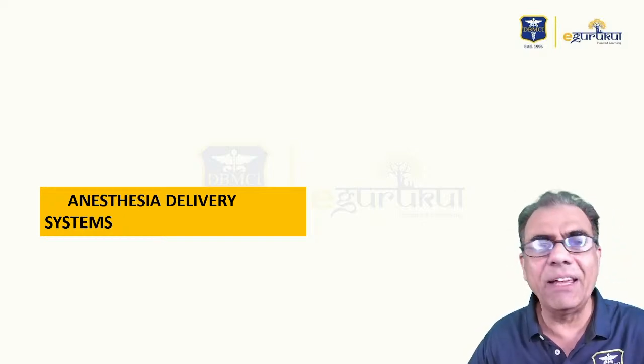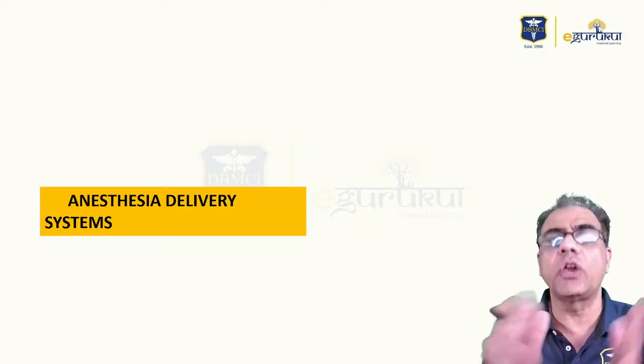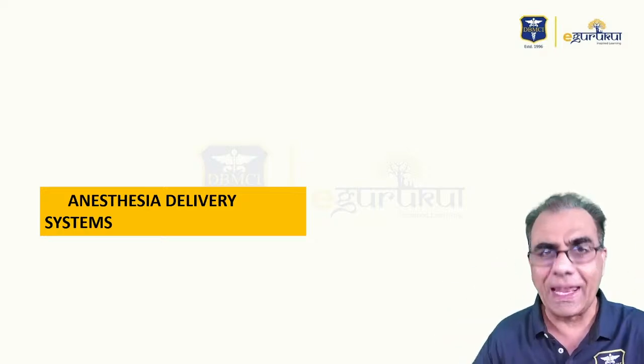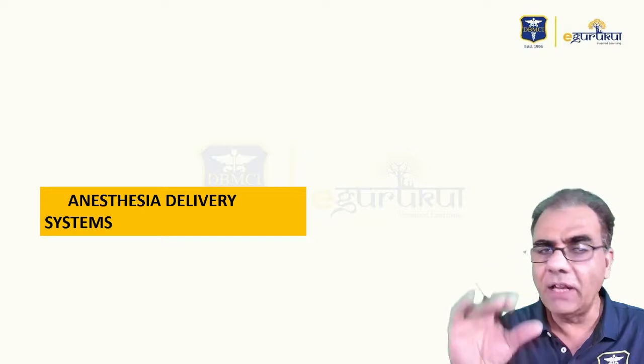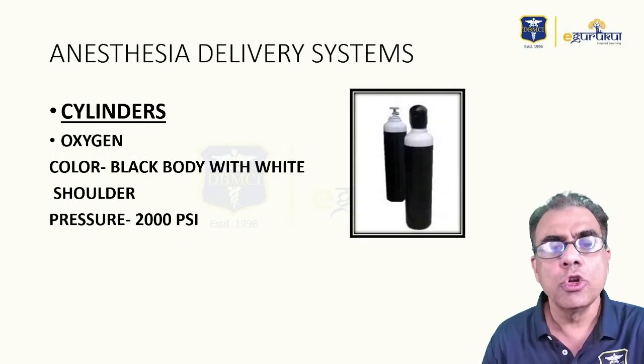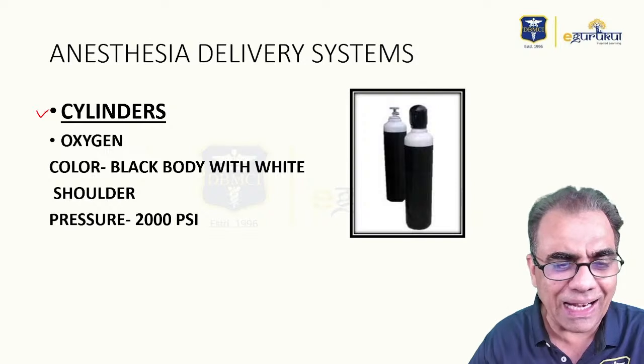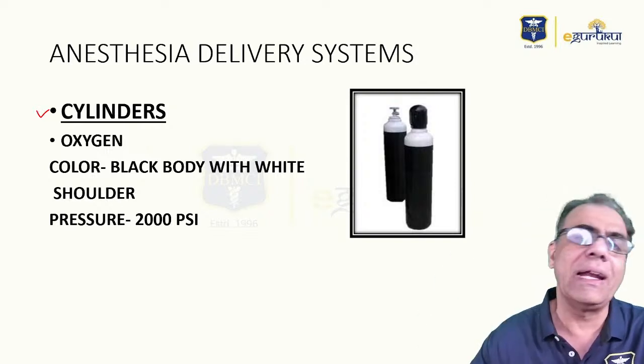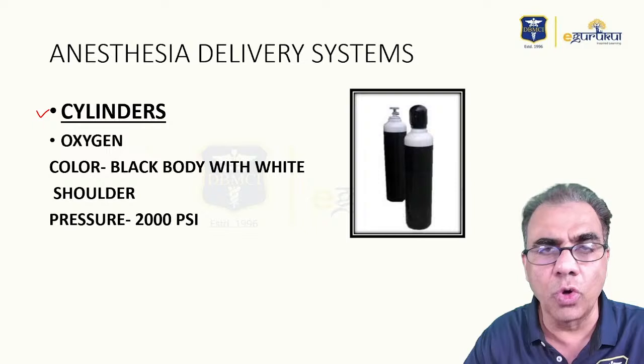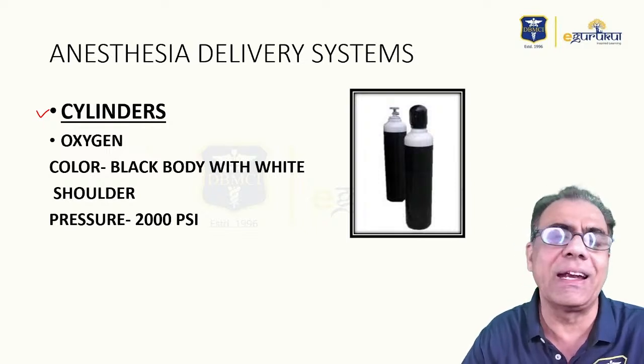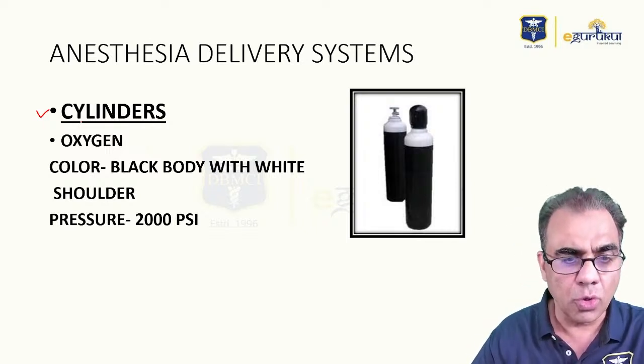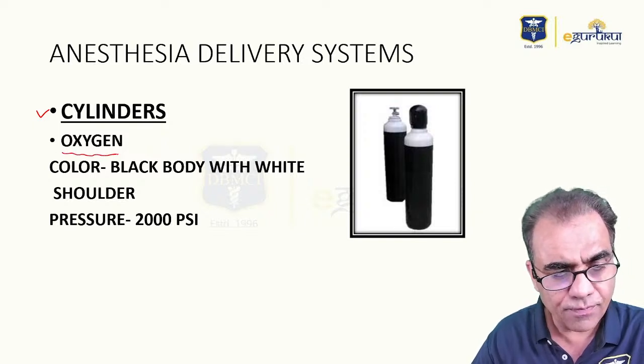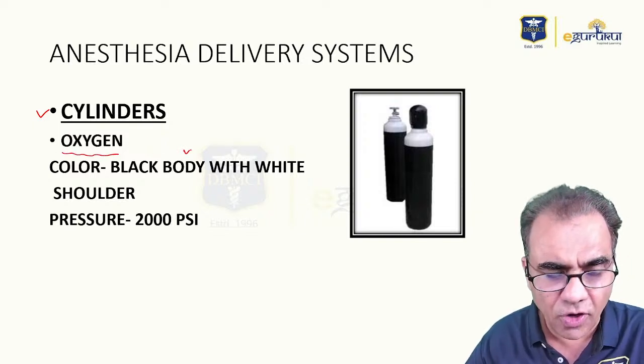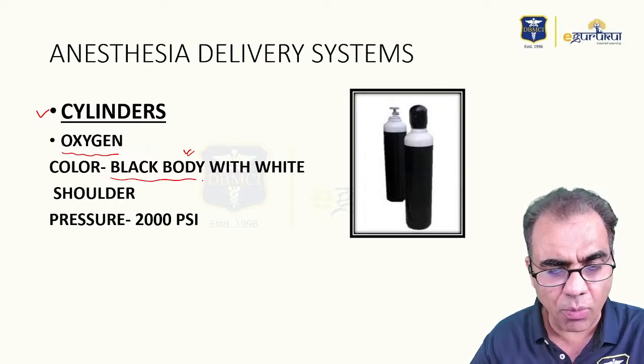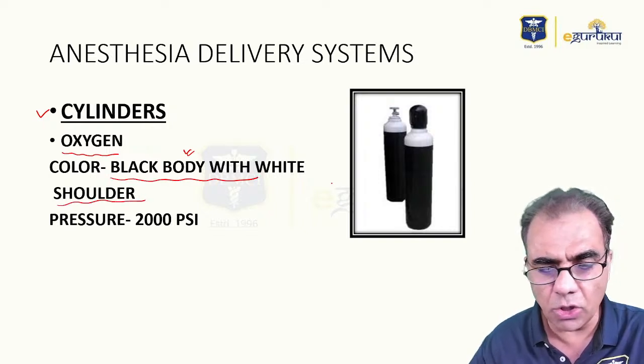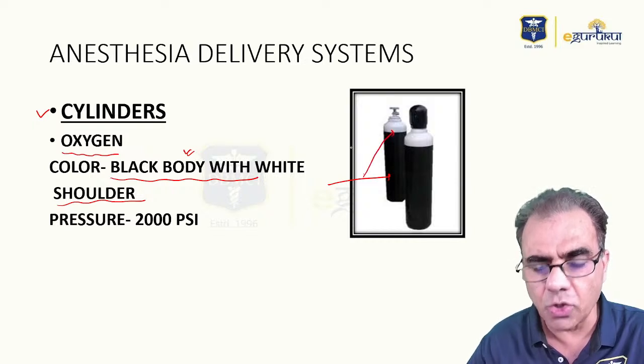Anesthesia delivery systems means, as the name suggests, the equipment which is used for the delivery of anesthetic gases. And to deliver something, you must have a source. So your source could be cylinders. Regarding cylinders, the two most important things that you should know are the color of the cylinder and the pressure of the cylinder. Let's start with oxygen. The color of the oxygen cylinder is black body with white shoulders.